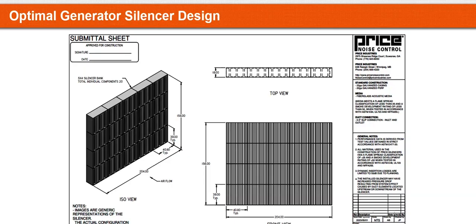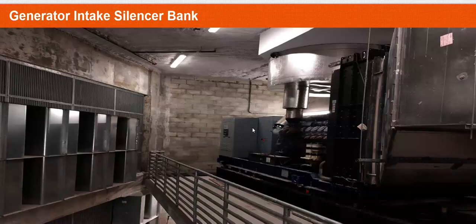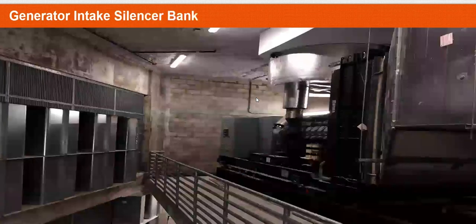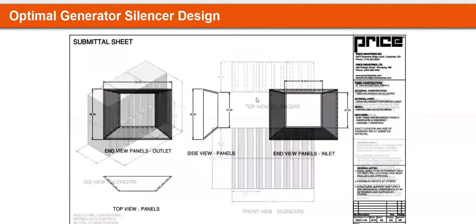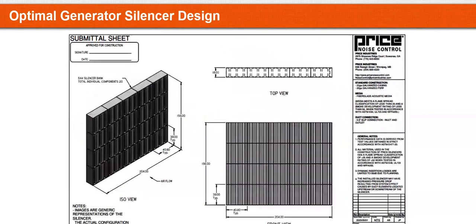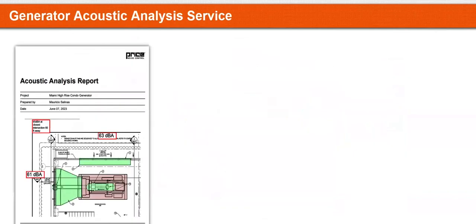In this case, the airflow was such that the opening allowed for the face velocity going through the silencer and louver to be under 300 feet per minute. The pressure drop wasn't a tenth of an inch. Looking at the previous CFD, it was more like 0.05, allowing for the rest of the pressure the generator can account for to be used for your dampers, for your louvers, or any other element on the way.